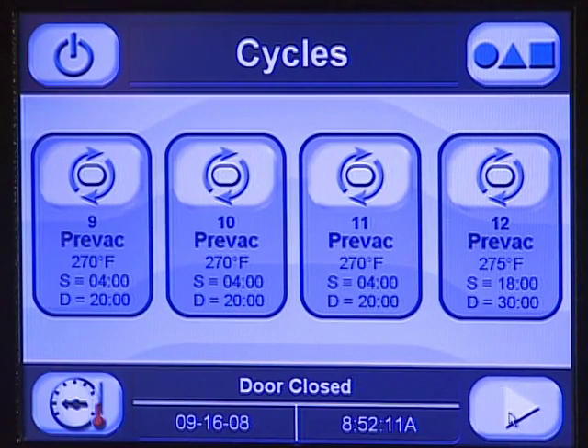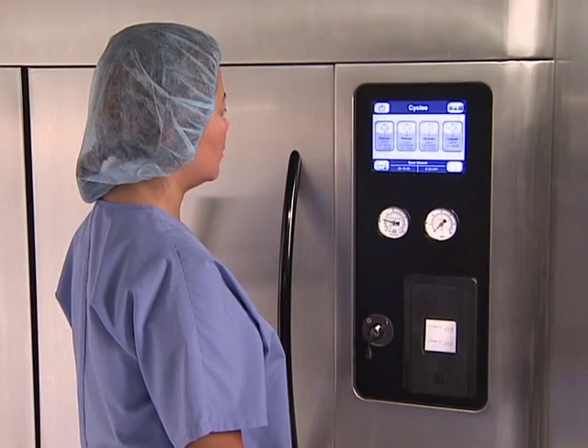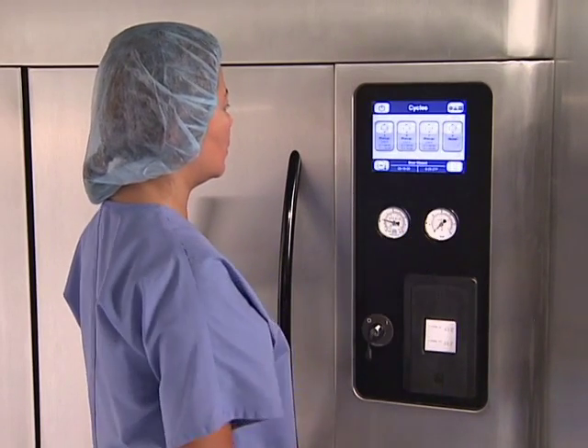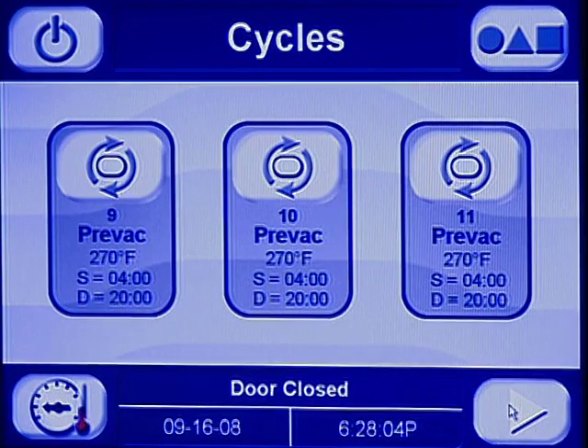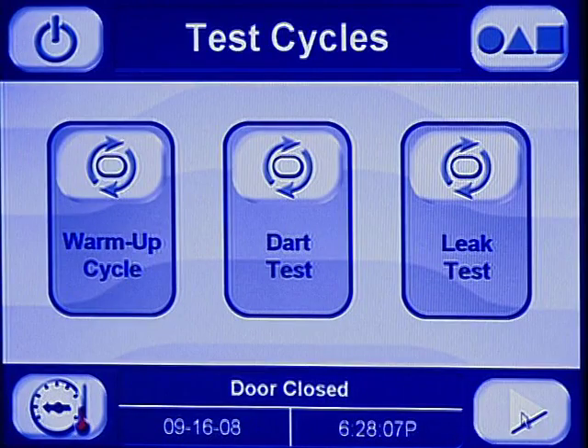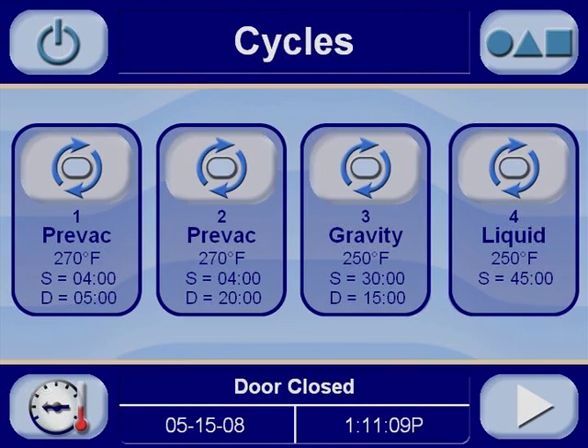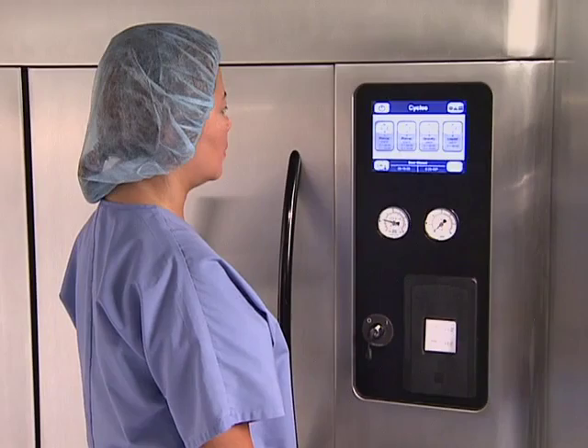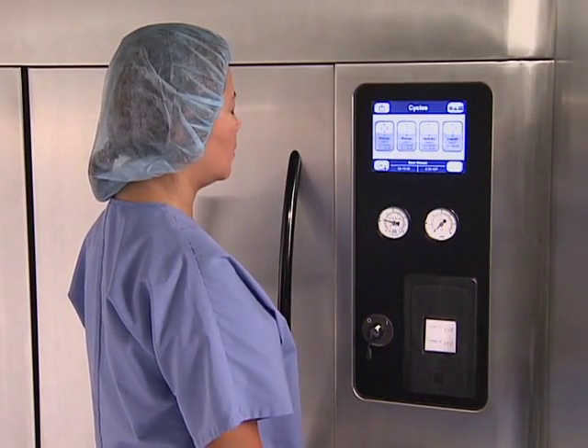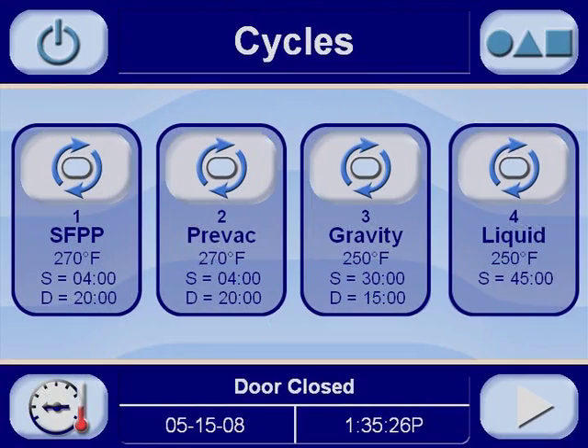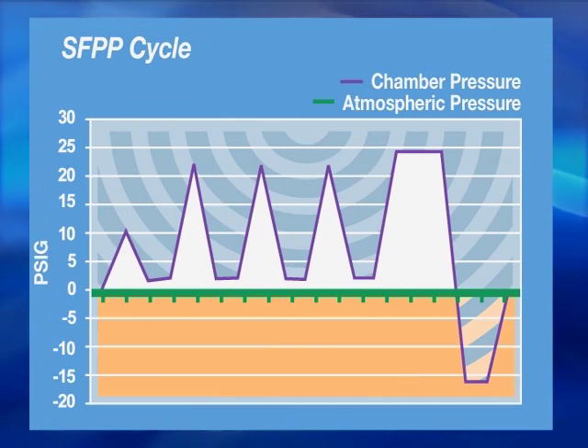The sterilizer has 12 pre-programmed cycles. 4 cycles are available in the initial cycle selection screen. To access additional cycles, including test cycles such as the Bowie Dick and vacuum leak tests, press the arrow in the lower right-hand corner of the screen. The Prevac and Gravity cycles are used for processing double-wrapped instrument trays, basin sets, and fabric packs. Which cycle you choose depends upon the instrument manufacturer's recommendations. Some Evolution steam sterilizers are equipped with an optional SFPP cycle that conditions the load with above atmospheric pressure steam pulses.